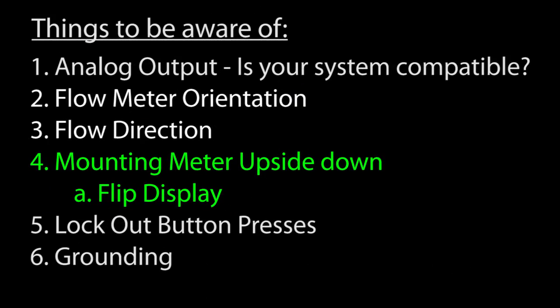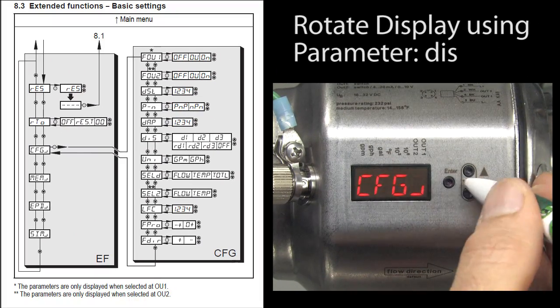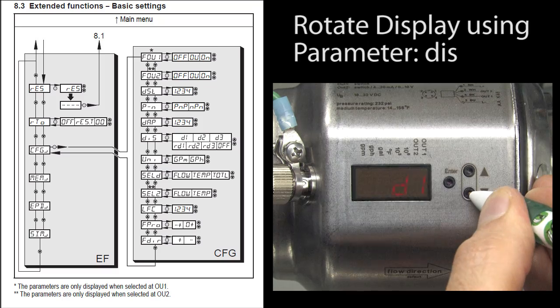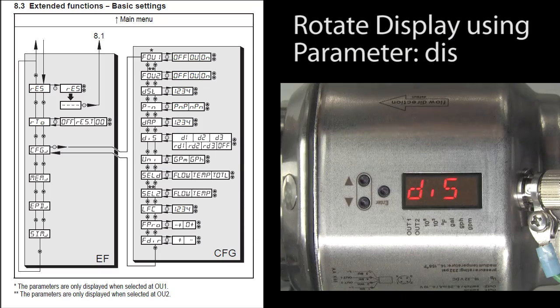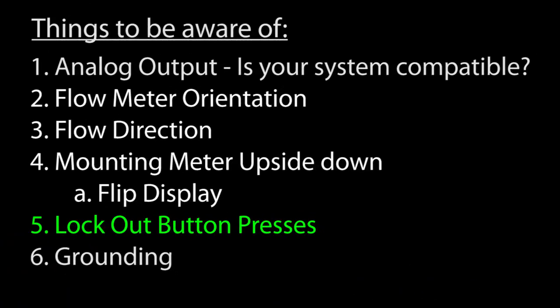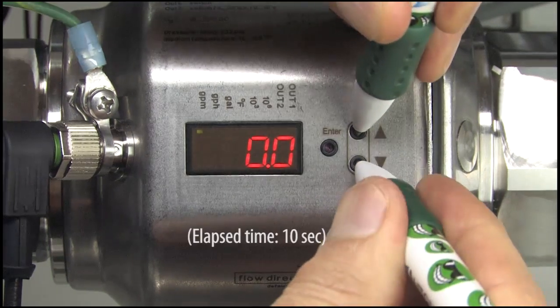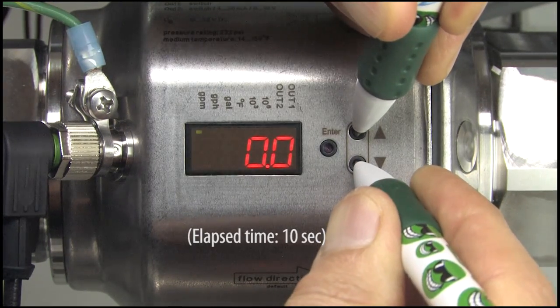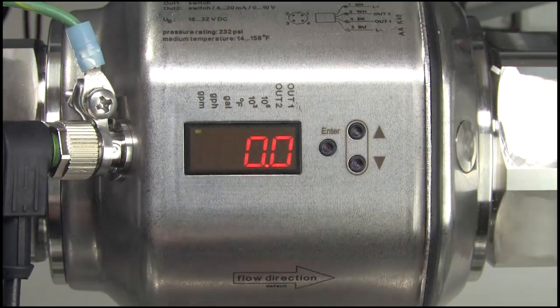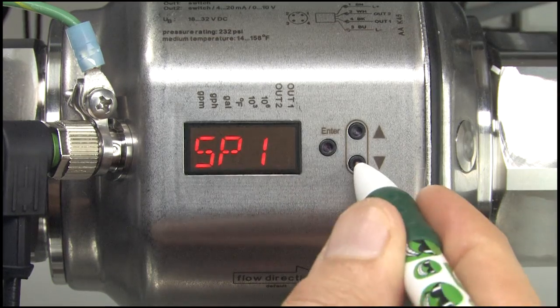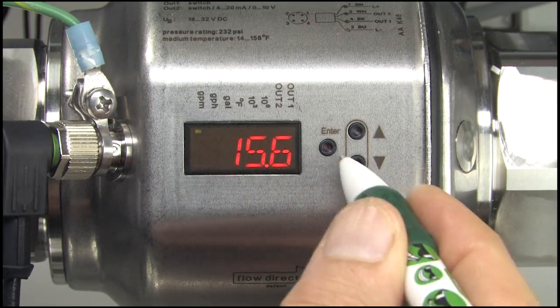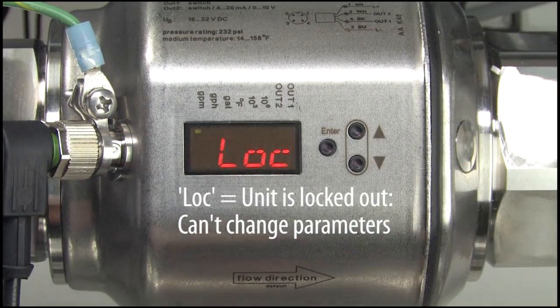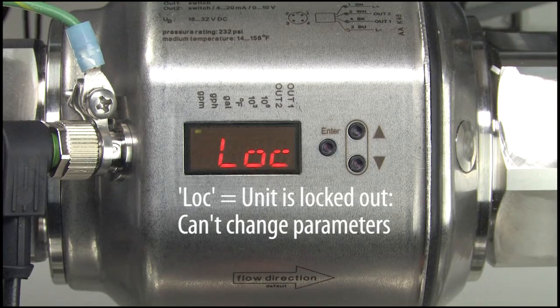You can mount the unit upside down as long as the flow is in the right direction and there is even a parameter you can set to invert the display to make it easier to read. You can lock out unintentional button presses by holding the up and down arrows for 10 seconds. To get it back, just hold the same buttons for another 10 seconds. This will allow folks to look at all of the menus and parameters, they just won't be able to change anything while it is locked out.